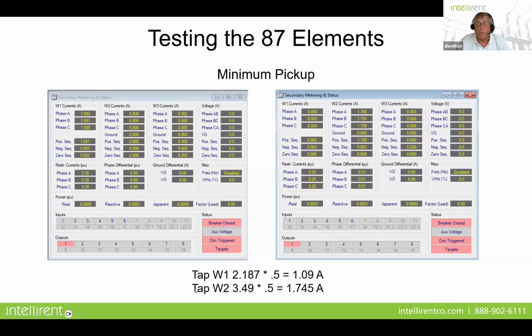And we do the same thing on winding 2. And this is no different than we did on our BDD or in our HU. Okay, it's just that it's 3-phase, not single phase. So you have to make sure you ramp all 3 phases simultaneously as you're doing this minimum pickup test. So that will verify the minimum pickup.